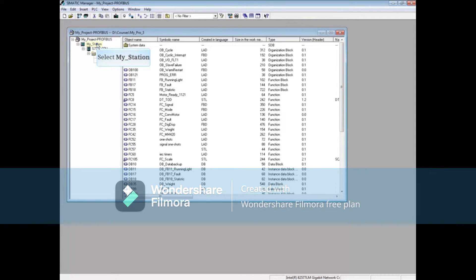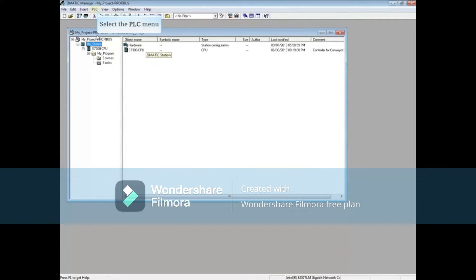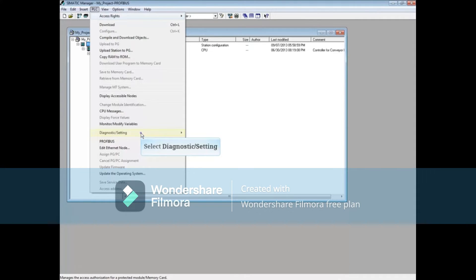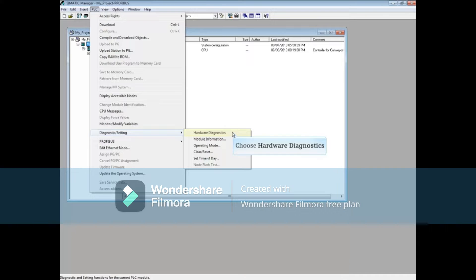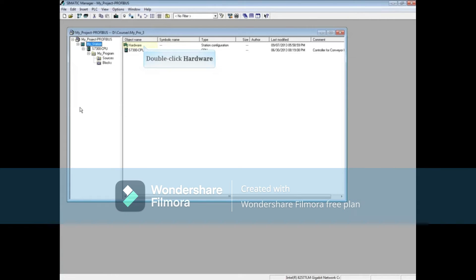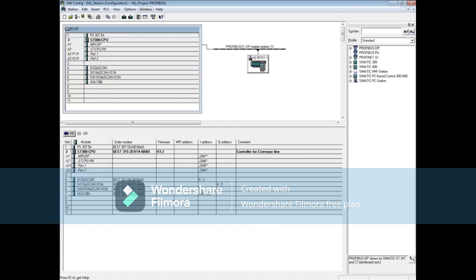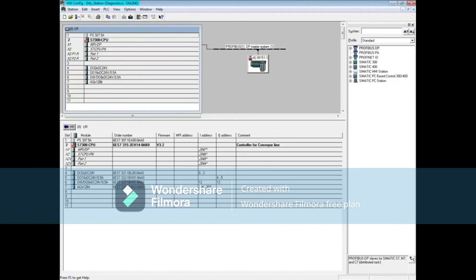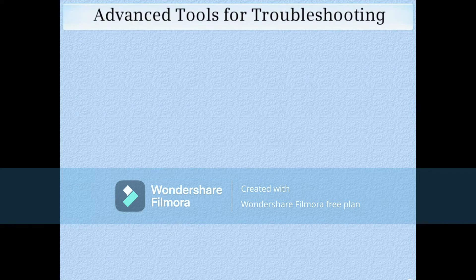Now let's talk about hardware-related errors. Select the station level of the project, open the PLC menu again, choose diagnostic settings, but this time choose hardware diagnostics. Any stations that have diagnostic information will show in this list. Highlight a station and click the module information button to bring up the diagnostics for that station. Alternatively, double-click hardware to open the hardware configuration editor and put it online to see a graphical representation of where there are faults on the system.